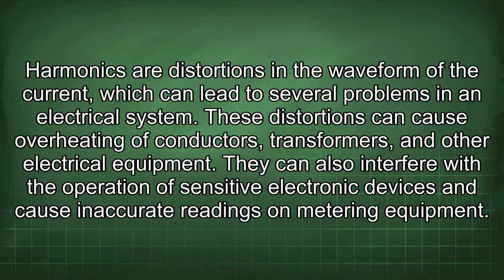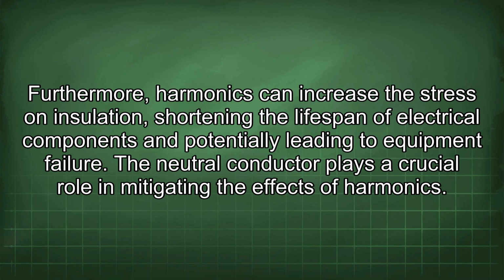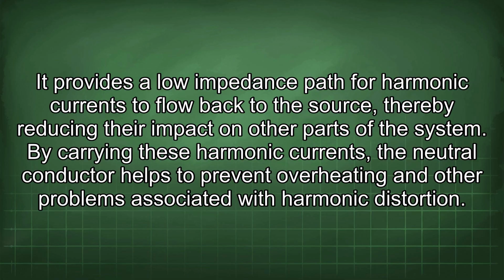Harmonics are distortions in the waveform of the current, which can lead to several problems in an electrical system. These distortions can cause overheating of conductors, transformers, and other electrical equipment. They can also interfere with the operation of sensitive electronic devices and cause inaccurate readings on metering equipment. Furthermore, harmonics can increase the stress on insulation, shortening the lifespan of electrical components and potentially leading to equipment failure. The neutral conductor plays a crucial role in mitigating the effects of harmonics. It provides a low impedance path for harmonic currents to flow back to the source, thereby reducing their impact on other parts of the system. By carrying these harmonic currents, the neutral conductor helps to prevent overheating and other problems associated with harmonic distortion.